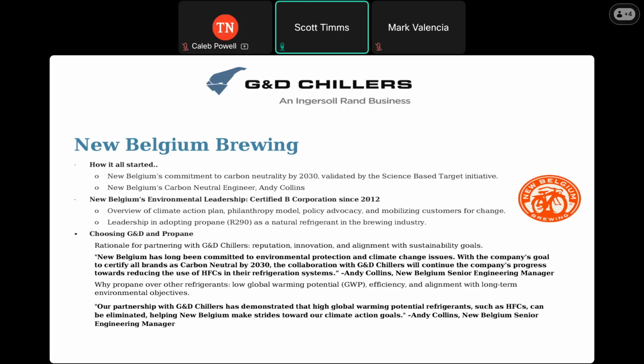A little background on why we're even thinking propane: essentially, in the last 20 years, the main refrigerant used has changed three or four times. You might remember, if anyone here is old enough, refrigerants putting a hole in the ozone, so there were a lot of changes to move away from ozone depletion potential, or ODP. We moved to refrigerants with essentially zero ODP. But now the issue with refrigerants is global warming potential. The way global warming potential is defined: one pound of CO2 in the atmosphere has a global warming potential of 1, and other chemicals are compared to that.